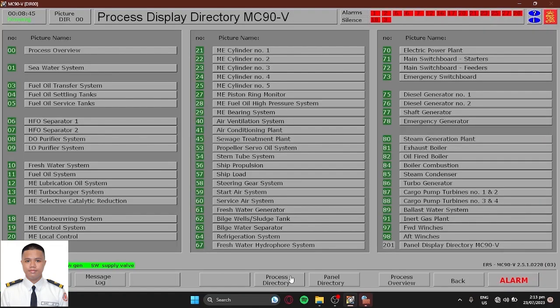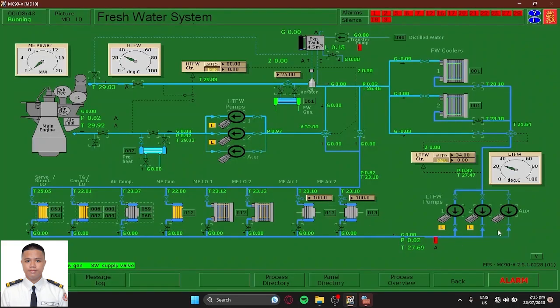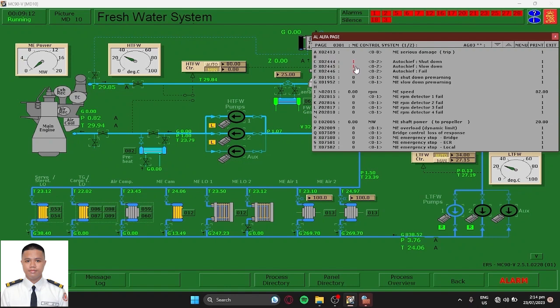Next step is to check our freshwater system as well. In the freshwater system, notice how our aux pump also turned off. So what we're going to do here is the same as seawater system. Turn this main pump on. Wait for the pressure to rise. There we go. Auto it. Then press remote these two pumps. Turn all these valves on except for MELO2. So let's turn it on. Acknowledge these alarms.